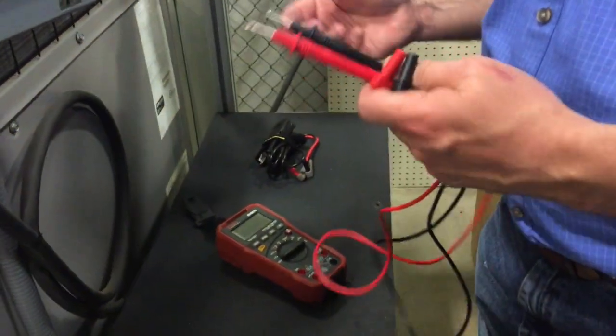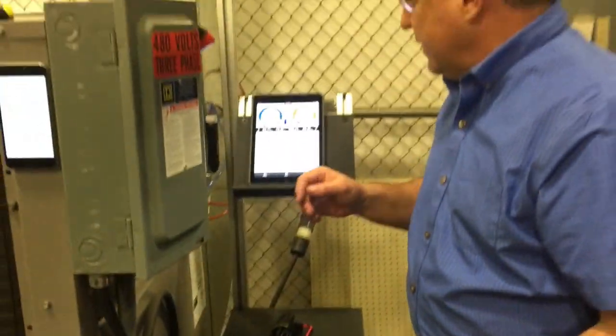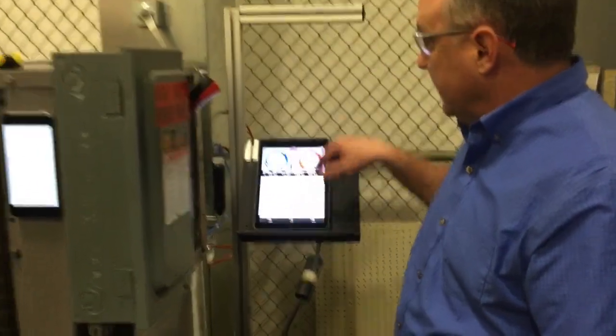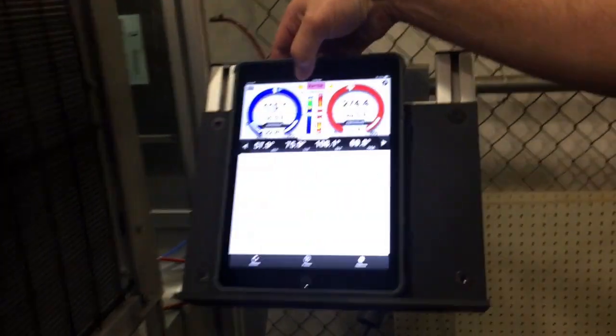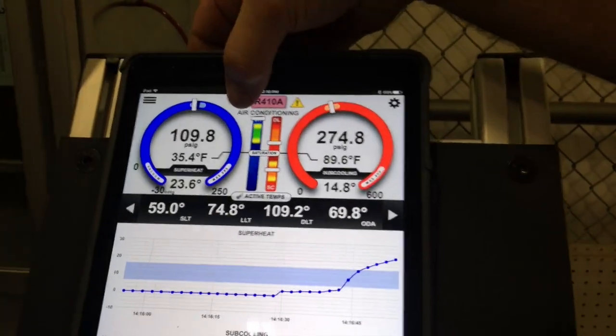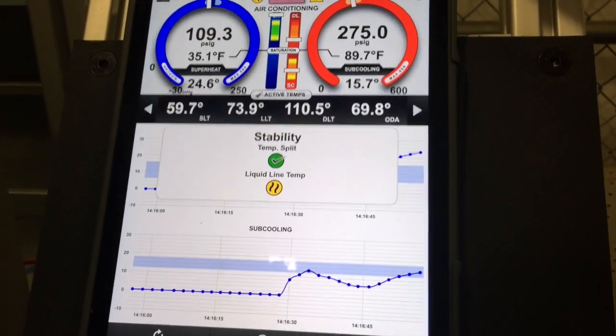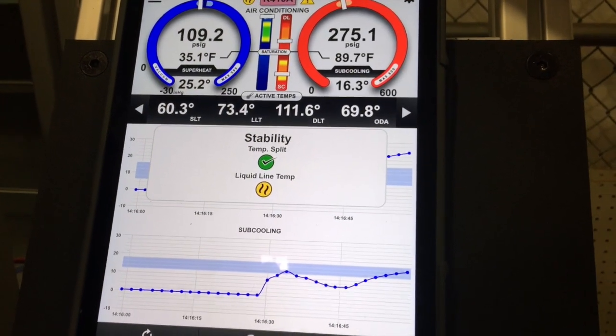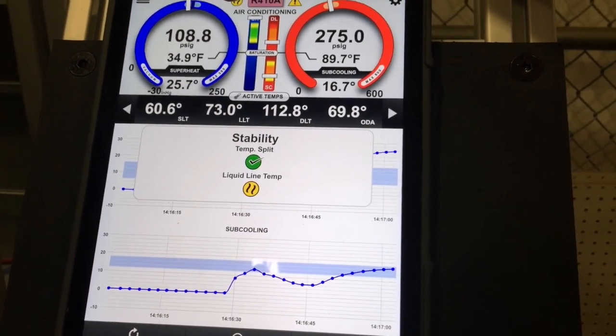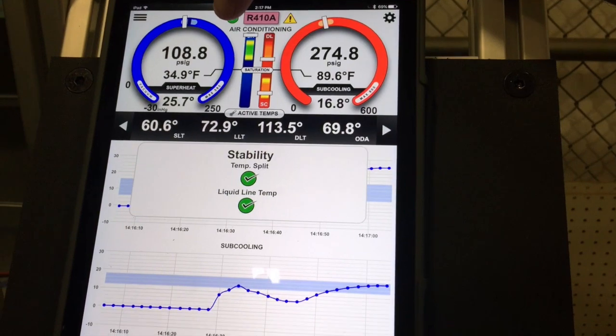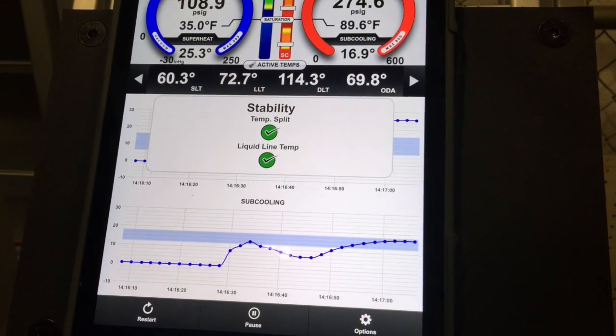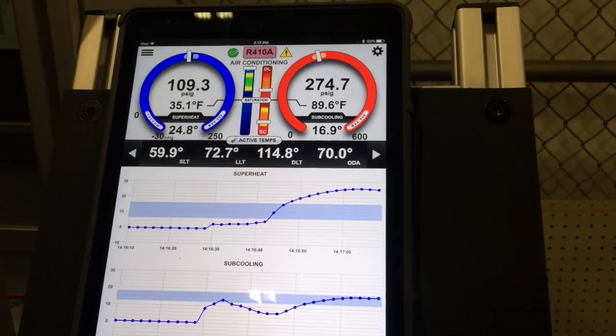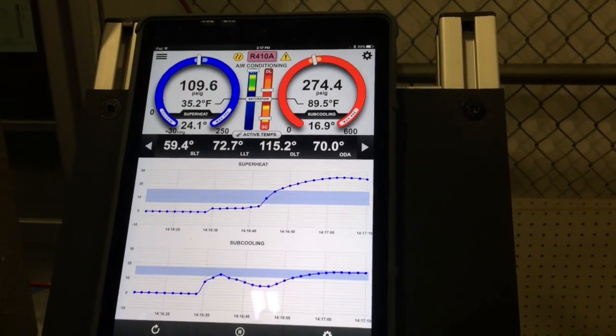So I'm going to show you how the system's stabilizing, and just a couple of quick notes here. On the iManifold application, this is a stability indicator. If I touch that indicator, you can see that we're looking for a stable temperature split and stable liquid line temperature. Those will change as it goes on a little bit, and we're waiting for the system to stabilize. So we're going to give it a couple minutes, and then we'll go ahead and do the testing.